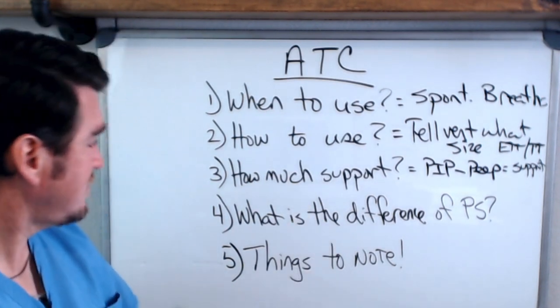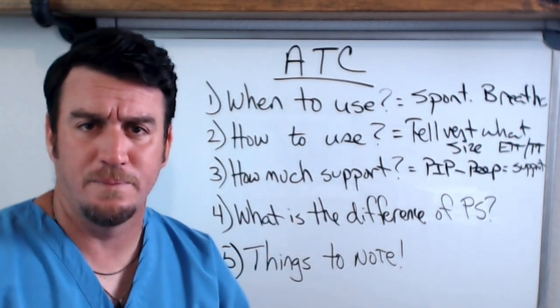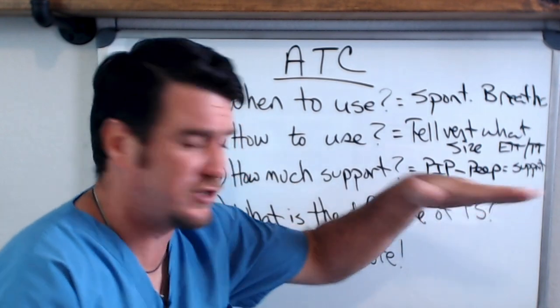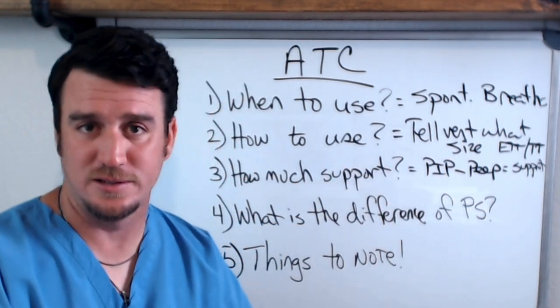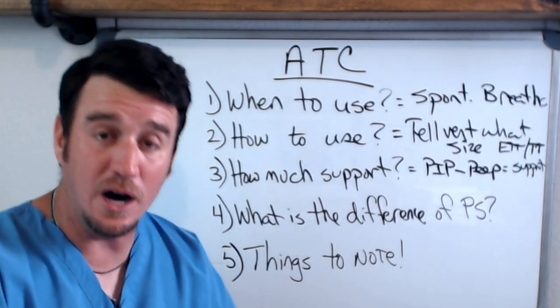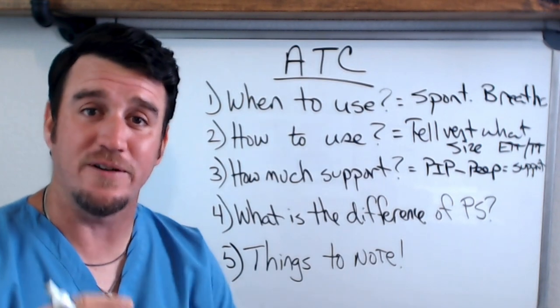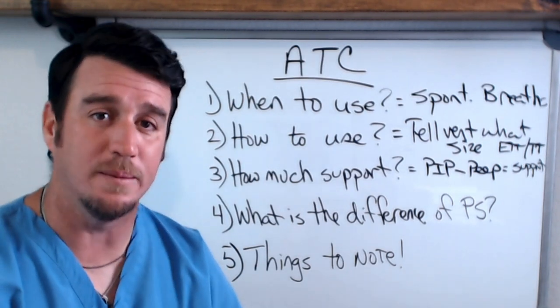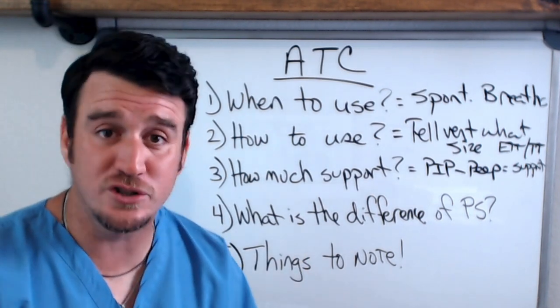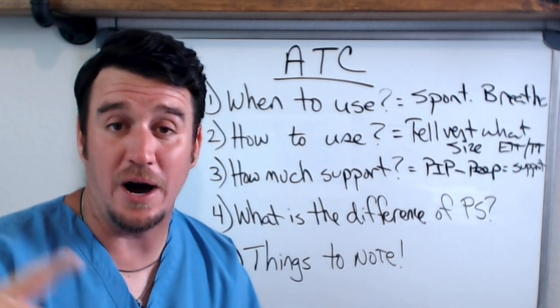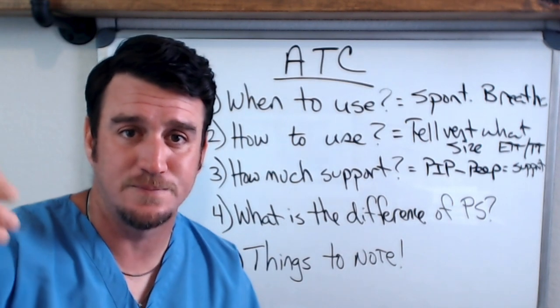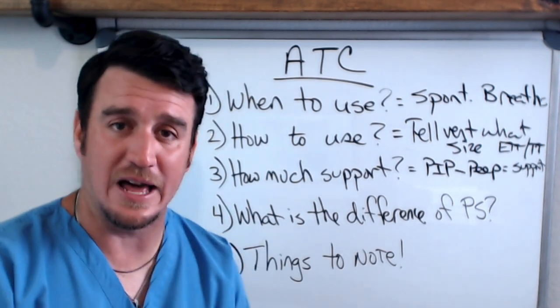Another question I get is: what's the difference between ATC and pressure support? ATC takes into account the artificial airway and provides just enough support to overcome the calculated resistance of that airway. Pressure support just tells the vent: upon inspiration, increase the pressure by this set amount and then cycle off and allow for exhalation.